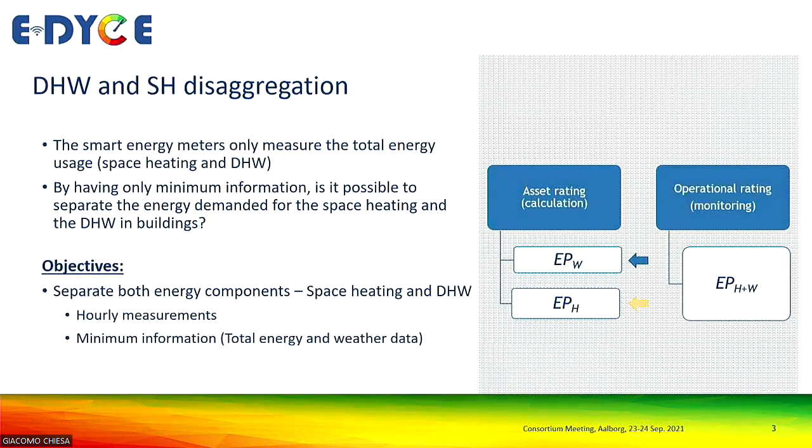And one of the challenges that we were looking into is the disaggregation of the data. As Michael has already mentioned to you, what we often look at is that we would like to compare the energy performance of the building, which is monitored, to the simulated data. If we look more specifically at space heating and domestic hot water use, very often we have a big challenge in monitoring the domestic hot water use in the buildings, because most of the smart meters that we know within the buildings measure the total energy, so combined heating and domestic hot water.